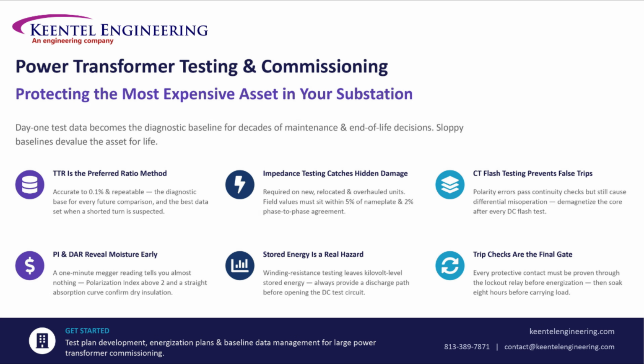Let's wrap this up. A power transformer is one of the most expensive assets in any substation, and it cannot simply be bolted down, filled with oil, and energized. Every piece of test data collected before that first energization, ratio, impedance, winding resistance, insulation readings, becomes the diagnostic baseline for the rest of that transformer's life. Get sloppy here and you're devaluing the asset for decades.